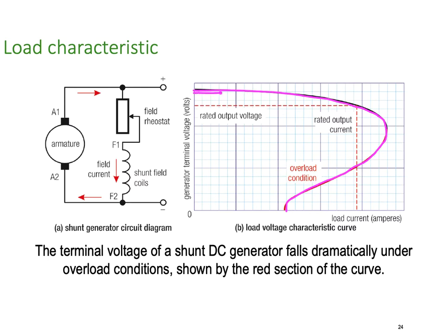It works well. So here, the flux is building, the flux is building, and then everything's cool as long as we stay here. But if you overload the generator, it slowly starts to slow down physically until it stalls, as it's called, or stops. And we end up here. So here's our circuit diagram. Our armature provides current to the load out through here, but it's also providing current to the field. And we can put a field rheostat in if we want to control that field current as well.